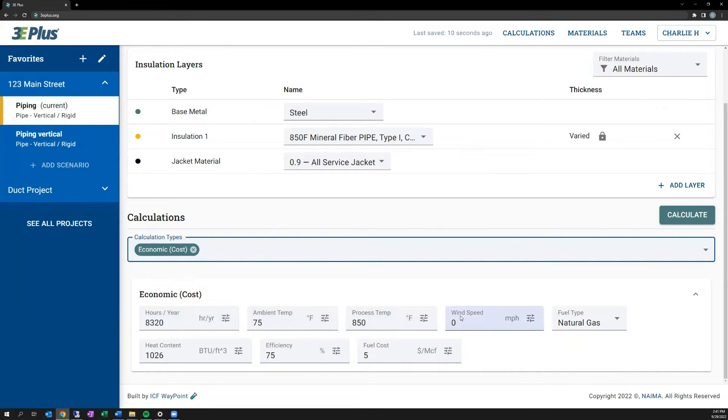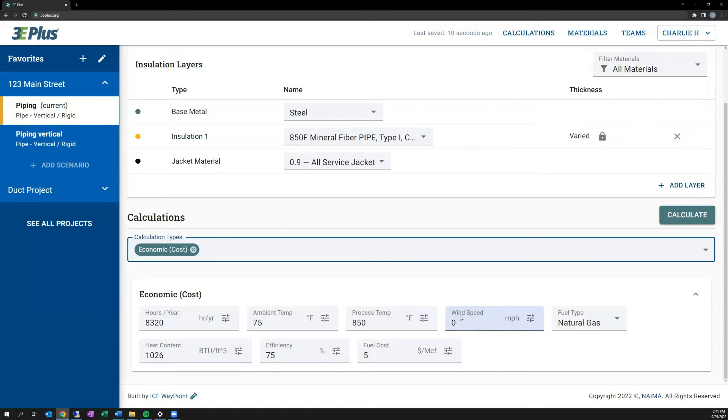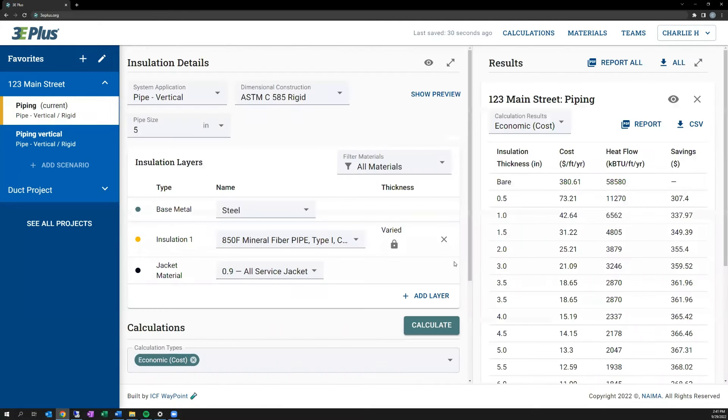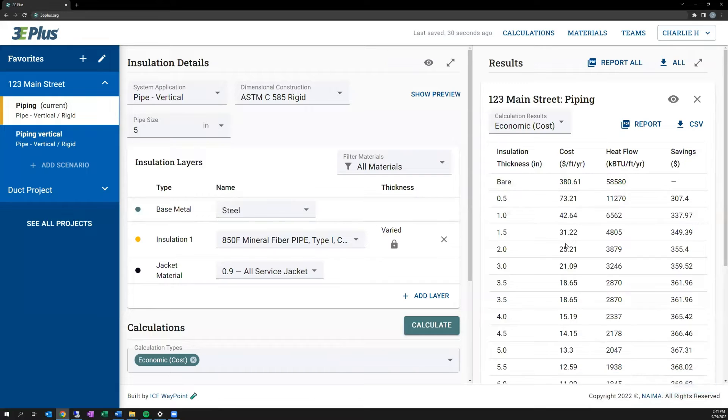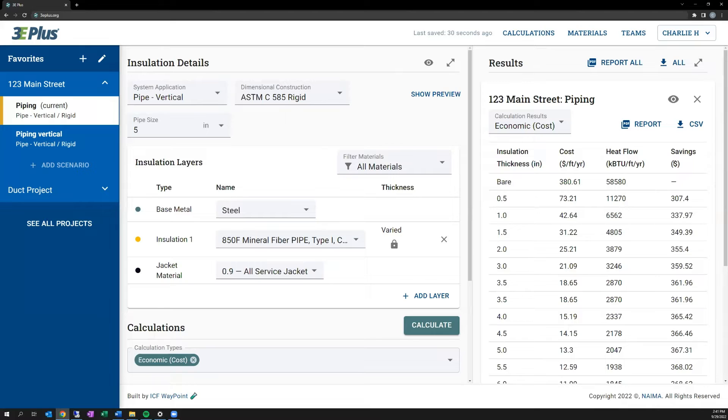But now you need to input the fuel type that's being used, the efficiency of the system, and the cost of fuel. This calculation type will take that information and give you a cost per year to operate, and the savings associated with insulating. So if I click Calculate here, with the values input, you'll see that it gives me an annual operating cost per foot, heat flow through the foot, heat loss, and then the savings versus an uninsulated pipe.